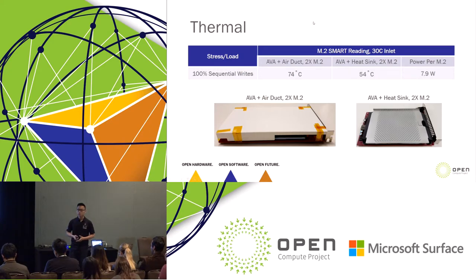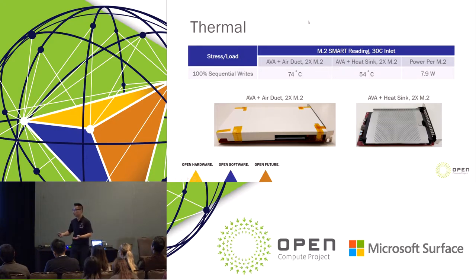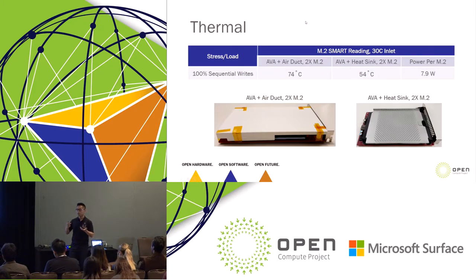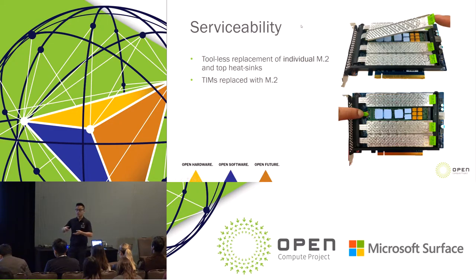This was what we were going with for a long time, but one of the issues we encountered — one of the lessons learned — is if you think about a service flow: let's say you want to replace a specific M.2. You pull the card out and replace that M.2, but the problem is thermal pad pre-compression. The other M.2s have been installed for a long time and their gap pads have been pre-compressed. When you install a new one, we found that performance degrades. That wasn't acceptable because we wanted it to be serviceable. So that's how we came up with a four heat sink design — one heat sink per M.2 — which gives us the ability to replace or add individual M.2s.